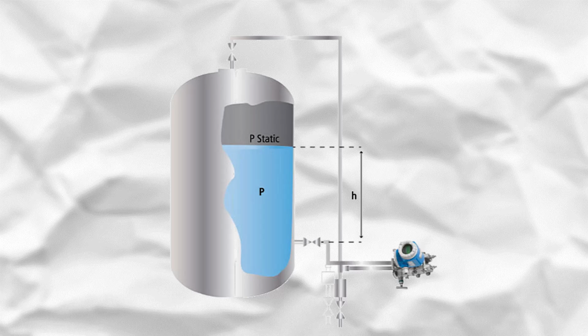Looking at my previous speech, you may remember that differential pressure transmitters are really handy and versatile to measure flow and pressure drop. In order to measure the level, we can also apply them. We know the density of the fluid inside the tank, so we are able to calculate the height based on the pressure column of fluid inside the tank. By means of 2 tubes, we connect the nozzles to a 5-way valve manifold and differential pressure transmitter. As you may see, the upper leg is dry because there is no fluid passing through.